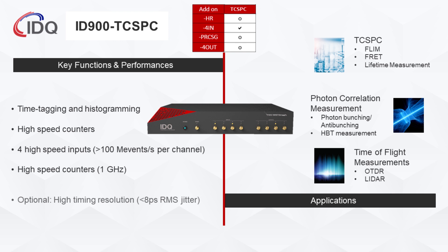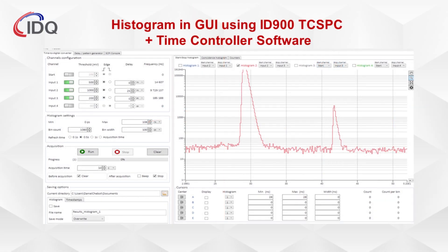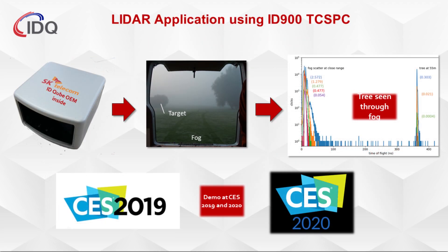With data throughput of 100 million events per channel per second, the ID900 can interface with high-speed detectors. The real-time histogram and time-tagging capabilities also enable time-of-flight measurements such as single-photon OTDR and LiDAR. This version is eligible for the high-resolution upgrade option, which enables minuscule 13 picosecond time bins, pushing the limits of single-photon experiments.